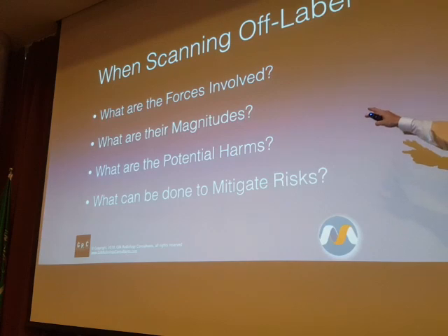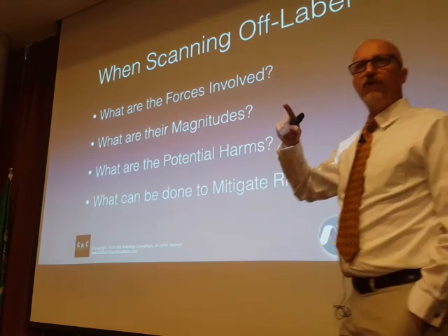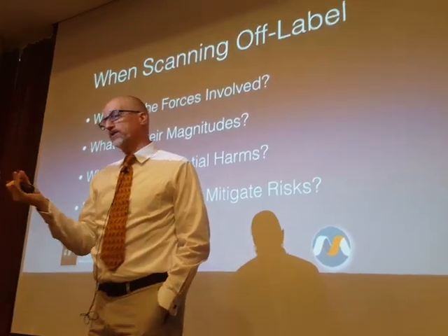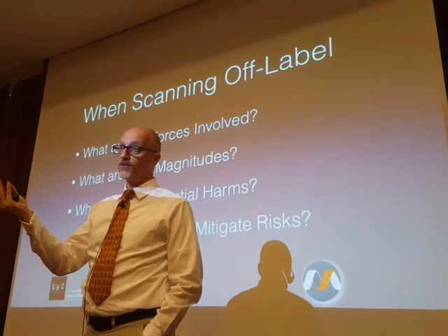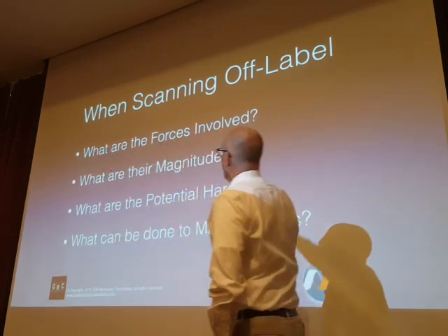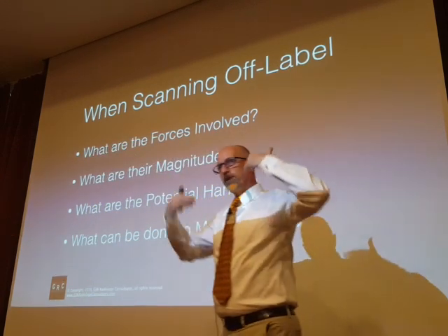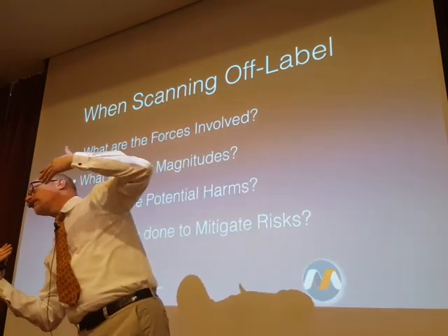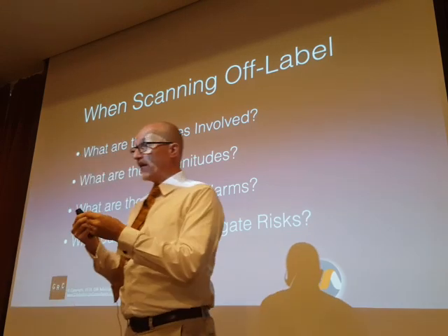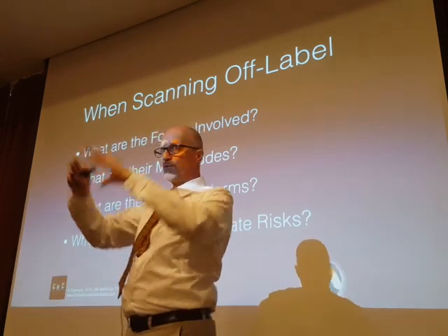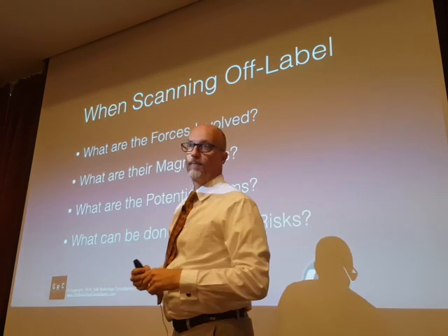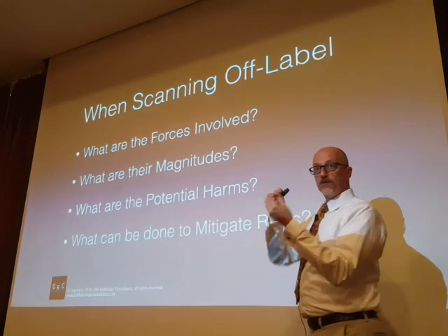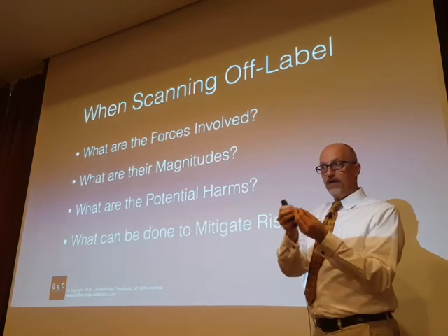So when you're scanning off-label, what are the forces involved? Our three forces — three buckets of potential risk — are static field, time-varying gradients, and radiofrequency. We can look at where the implant is within the body of the patient and how we're going to position the patient inside the magnet, giving us an understanding of where the implant is relative to the forces inside, and what their magnitudes are as they affect the implanted device.